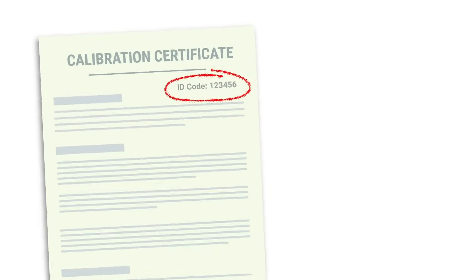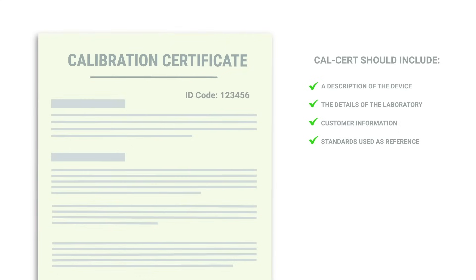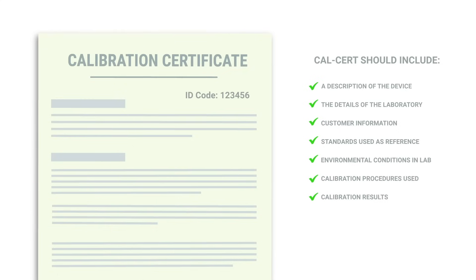The calibration certificate, or CALCERT, should include a description of the device, the details of the laboratory, customer information, a list of standards used as reference, environmental conditions during calibration, calibration procedures used, calibration results, and the name and signature of the technician who carried out the calibration.